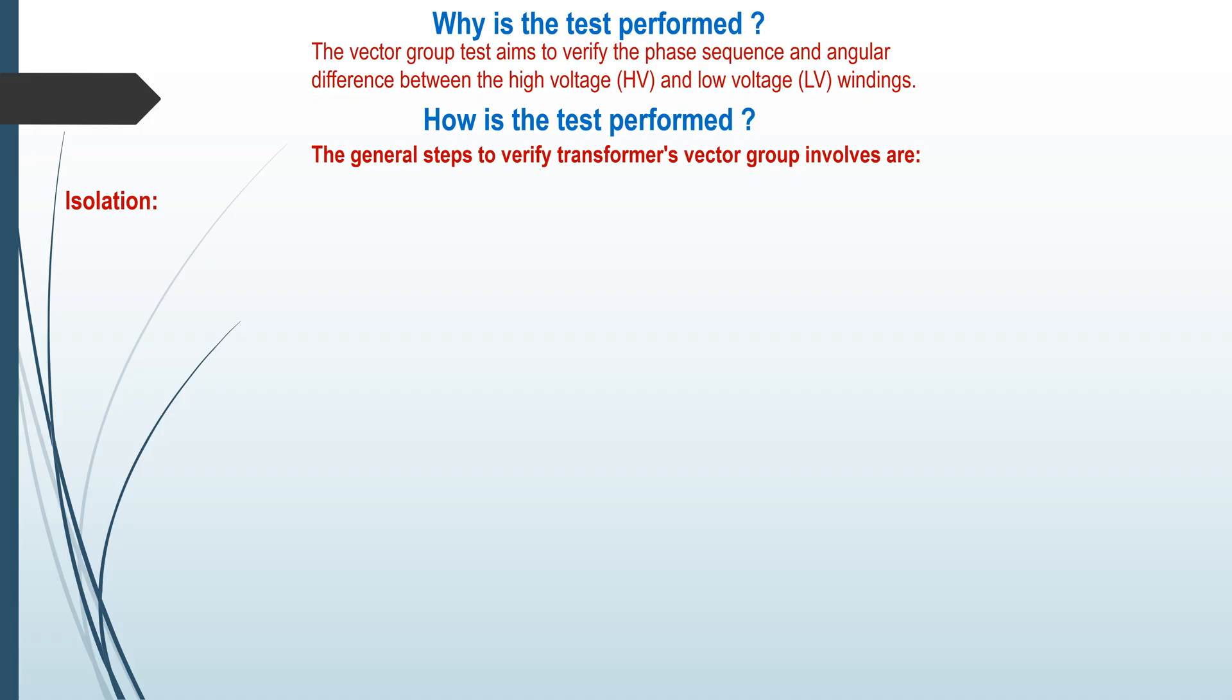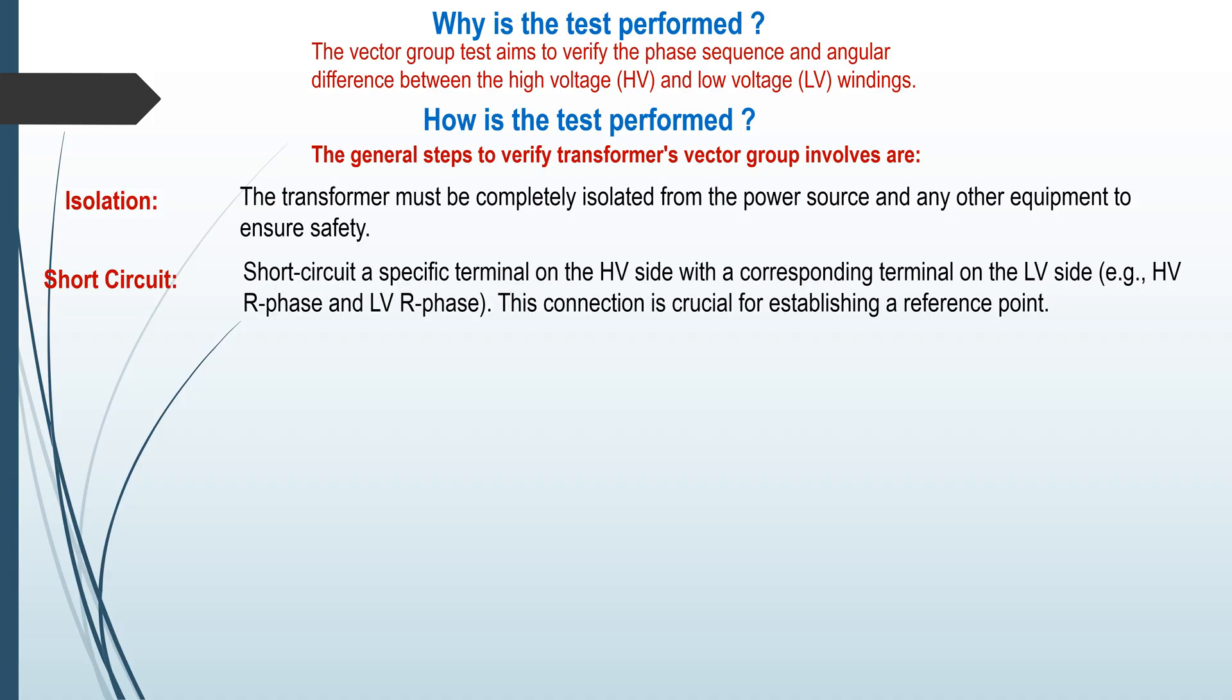Isolation: The transformer must be completely isolated from the power source and any other equipment to ensure safety. Short circuit: Short circuit a specific terminal on the HV side with a corresponding terminal on the LV side, for example, HV R phase and LV R phase. This connection is crucial for establishing a reference point.